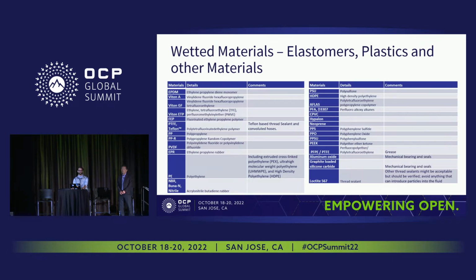Here is a summary of the elastomers, plastics, and other materials list. It's expected that these materials will primarily be used for components such as tubing, gaskets, and seals. The recommendations here are based on material compatibility and the temperature limitations of the system. The list between the two fluids is generally very similar, though there are exceptions with materials such as CPVC, which is not compatible with propylene glycol fluids.